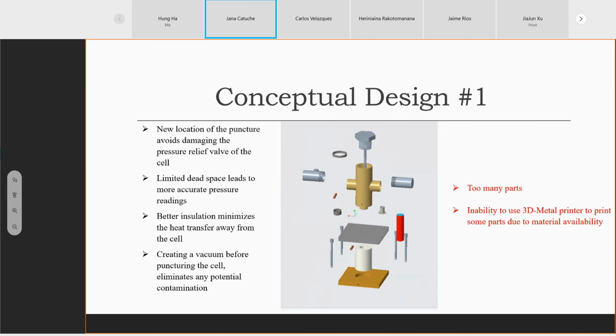Battery, so that the new location of puncture would avoid the pressure release valve, from the negative to the positive. This design also gives limited dead space, so it would lead to more accurate pressure readings. Hence this chamber, where the puncture would happen, automatically goes to the pressure transducer.